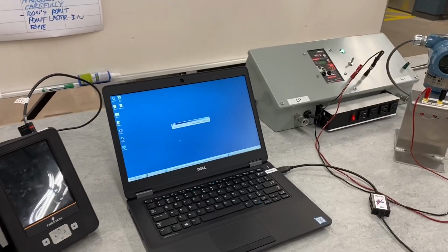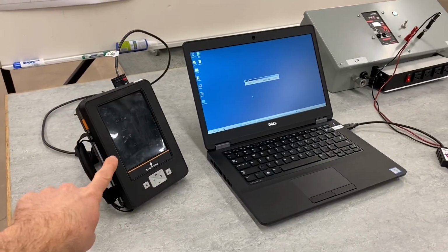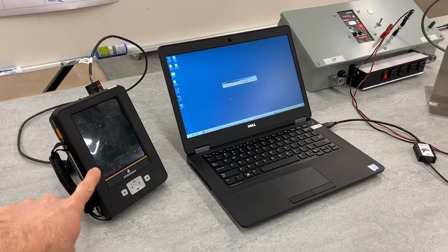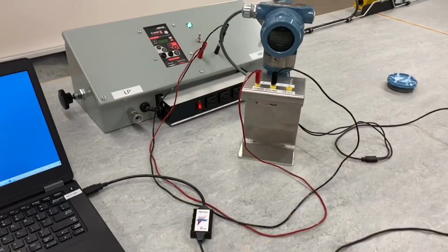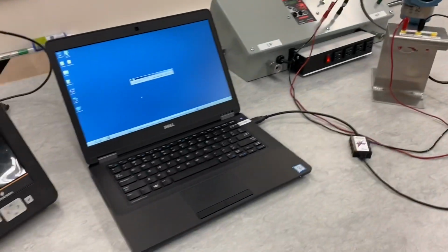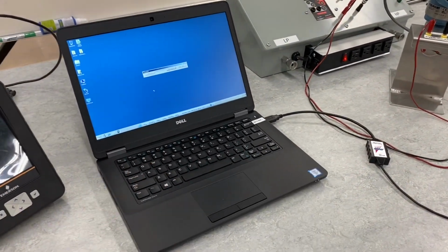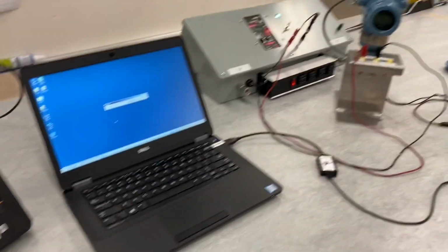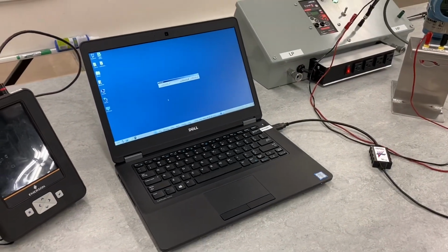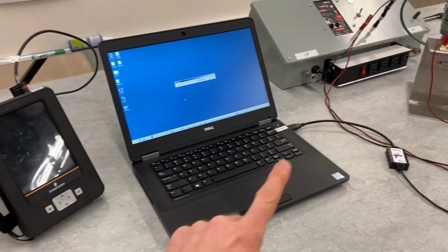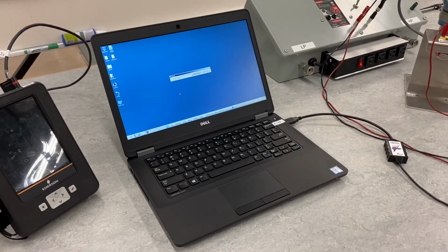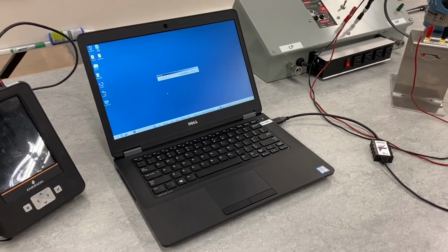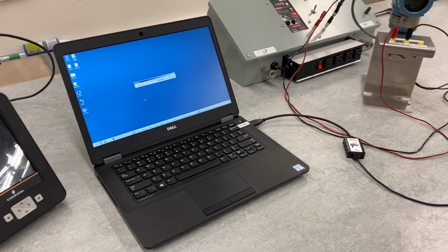In this video we're working with a Rosemount Emerson Trex communicator and a Rosemount 3051 pressure transmitter. We're going to add the pressure transmitter to AMS on our computer, and then demonstrate how the Trex communicator can be used to calibrate the device when it's offline from the AMS database. The communicator can talk to it, configure it, and then when we plug it back into the AMS main computer, we can upload all the changes we've made.